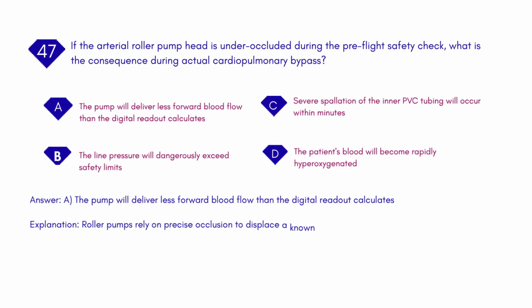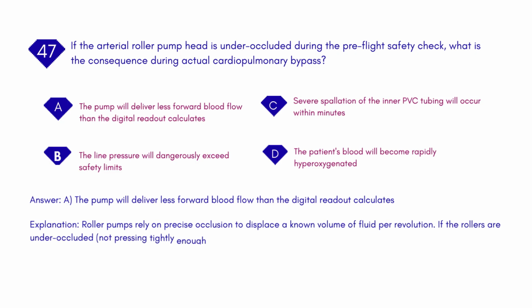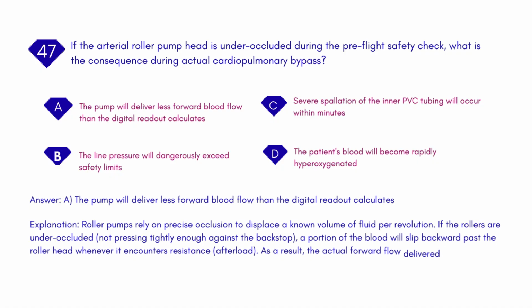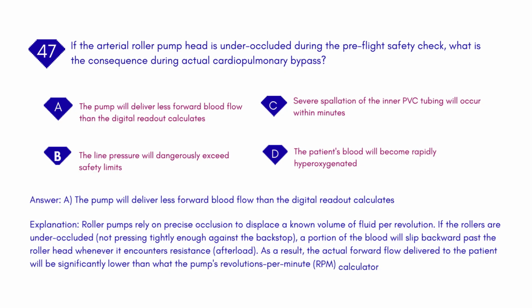Explanation: roller pumps rely on precise occlusion to displace a known volume of fluid per revolution. If the rollers are under-occluded, not pressing tightly enough against the backstop, a portion of the blood will slip backward past the roller head whenever it encounters resistance, or afterload. As a result, the actual forward flow delivered to the patient will be significantly lower than what the pump's revolutions per minute, RPM, calculator displays on the console.